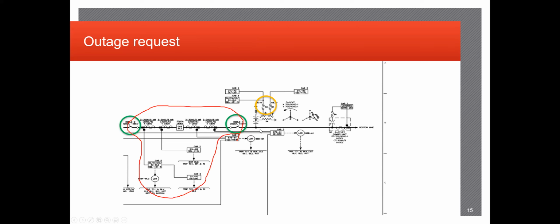So in this case, filling an outage request, we're going to be identifying the equipment. It looks like this breaker is going to be placed out of service to replace these relays, upgrade them, whatnot. So identifying here how this piece of equipment, or all these pieces of equipment, are going to be isolated. Mainly, the best way to do that is each breaker associated would have these switches shown here that would be opened up, and the breaker itself would also be open. That way no power is flowing in and out of this circuit, which would also leave the relays to read no currents, no voltages, and have no voltages or currents coming into the control house circuits as well. So that way, when the electricians or whomever go in to isolate and remove the equipment, nothing's going to be coming in and out.